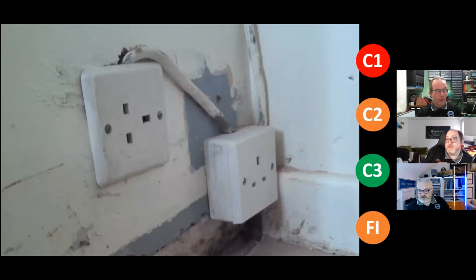Are we all going C3? C3, we've got 5% C2, 86% C3. And I could see why the C2s, if that was in a nursery or something like that. It's relative to where this is. This could be in a nursery. This could be in a cupboard. We're assuming domestic in this webinar.